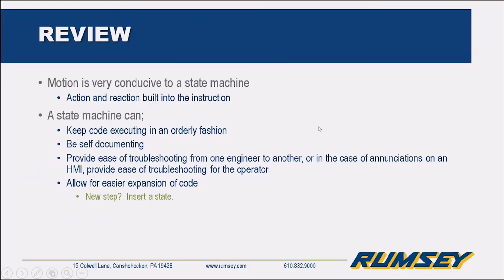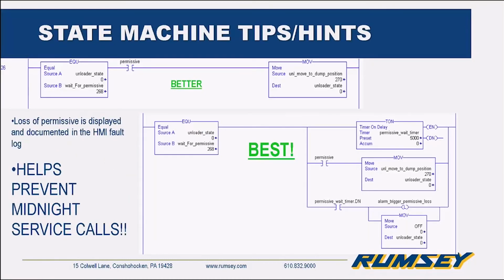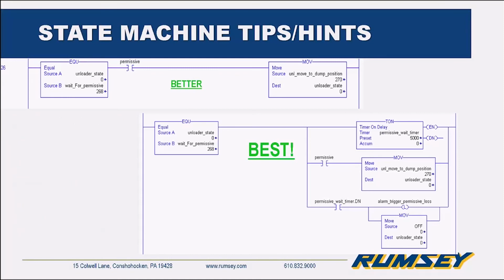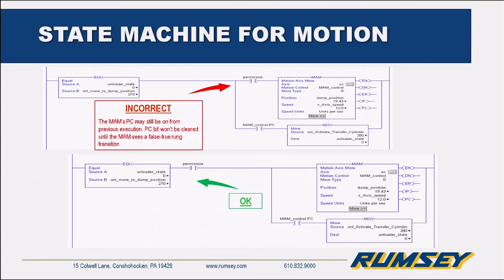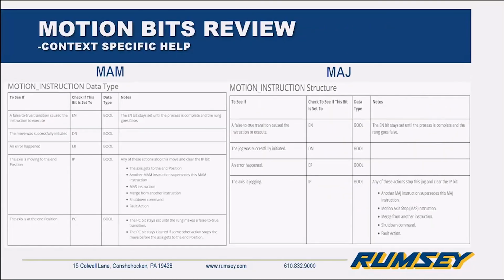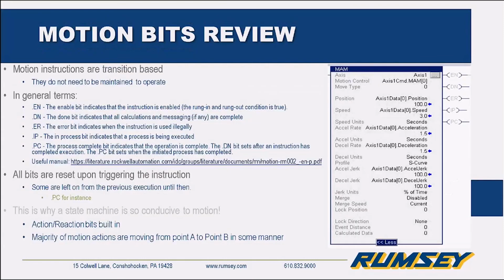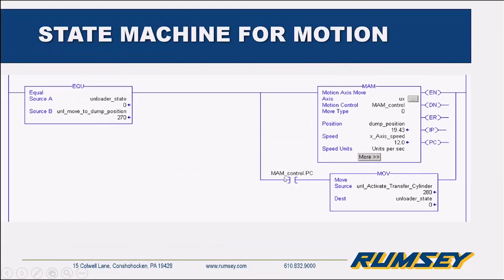Mike, what about if you go back one slide in the control words, which is your dones, your process completes, what about unlatching them independent of the instruction? What's your advice there? Oh, okay. Good thing Sean asked that. I didn't actually cover it. Do not unlatch bits. So please do not unlatch these bits. The state machine helps you deal with how they react. Do not unlatch. It can create funky actions. Just because you unlatch the bit doesn't mean internally to the instruction that it thinks the bit is unlatched. So point being, use them when appropriate.